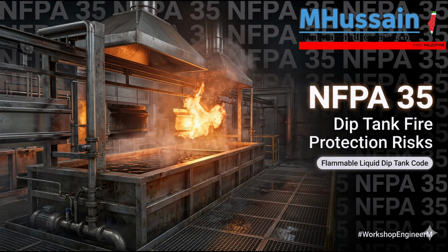So this is the temperature at which a liquid gives off enough vapor to form an ignitable mixture with the air directly above its surface. Just hovering right there. Right. So if you have a flammable liquid, which the standard categorizes as Class I, it has a closed cup flash point below 100 degrees Fahrenheit, which is about 37.8 degrees Celsius. Wait, below 100 degrees Fahrenheit? Yes. But I mean, 100 degrees is roughly just ambient summertime temperature in a lot of places. Exactly. And that is critical.